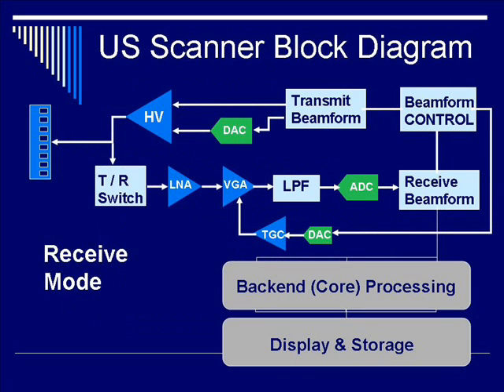Here again is the block diagram of the ultrasound scanner. During receive mode, you start off at the transducer end which receives the echoes from the various reflectors, as denoted by the red. It fans out to all the transducer elements, which in turn feeds in through the transmit-receive switch. In this case, the receive switch is turned on. The aggregate signal is then fed into the low noise amplifier, which we'll talk about in more detail under pre-amplification.